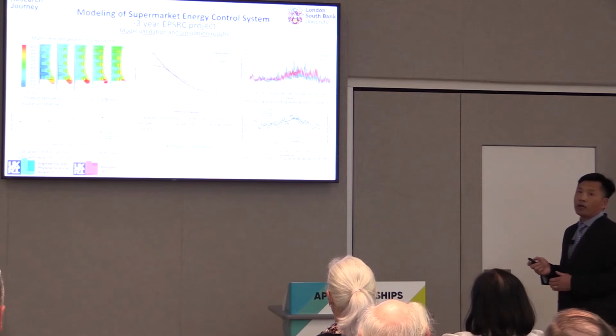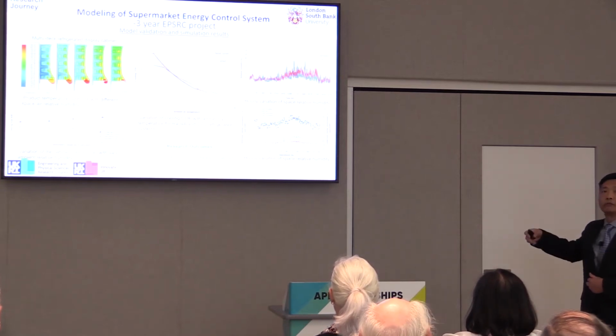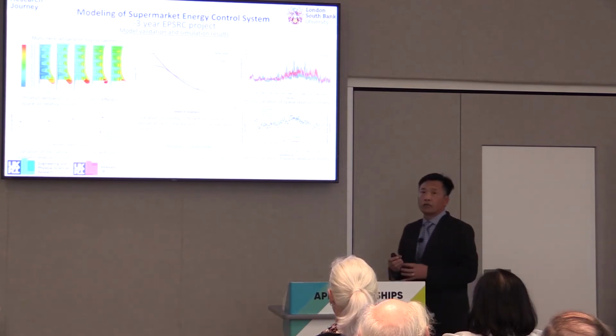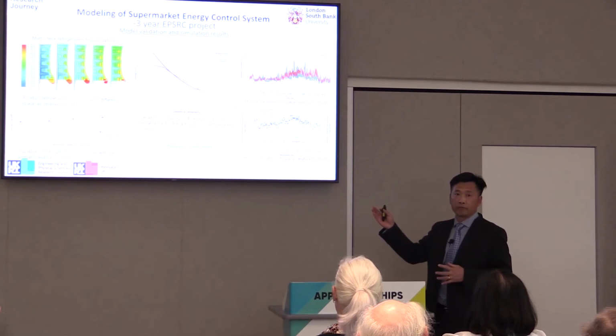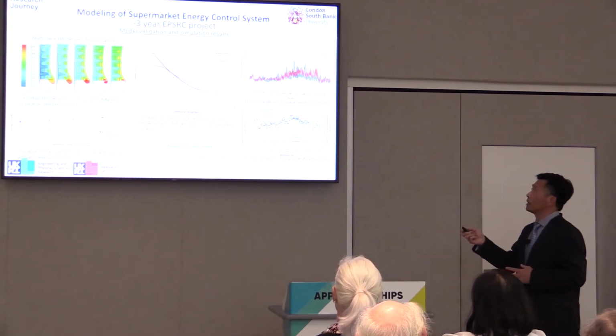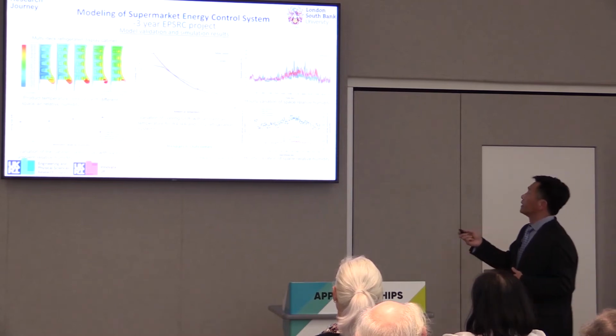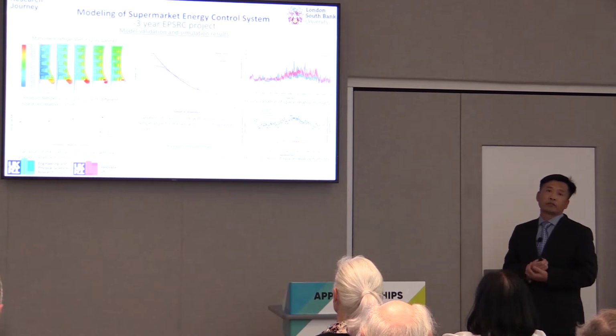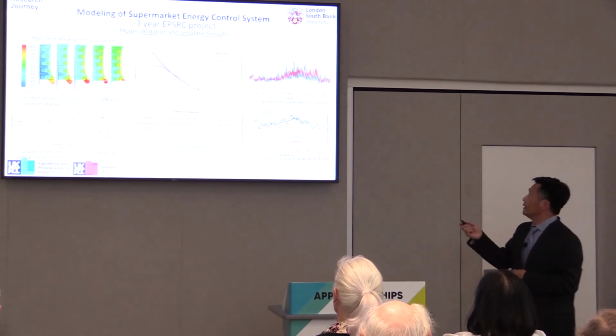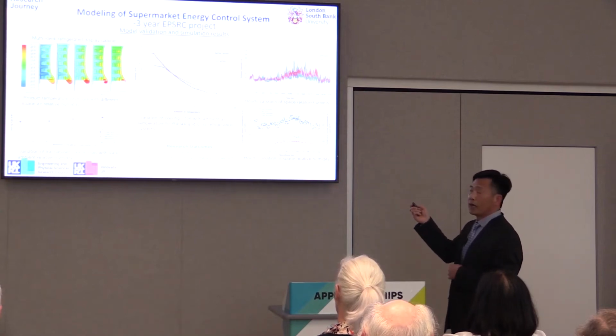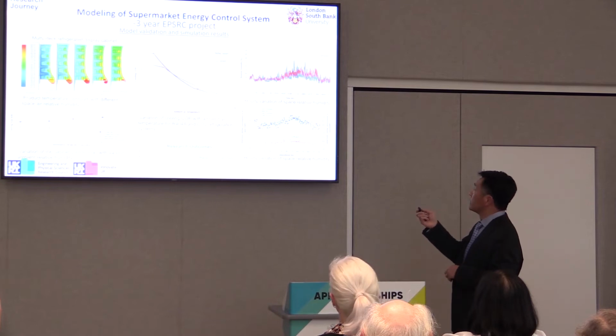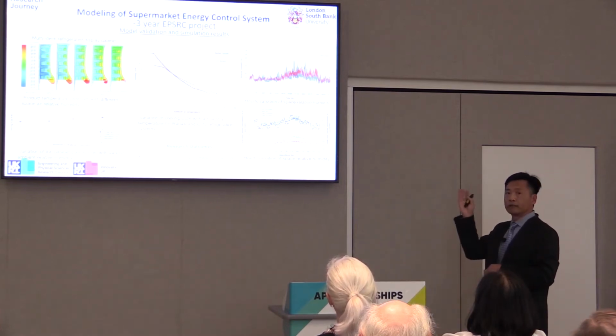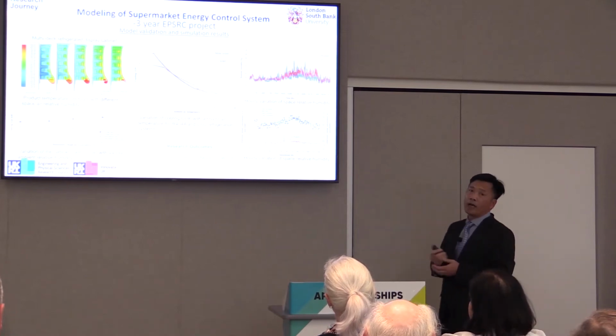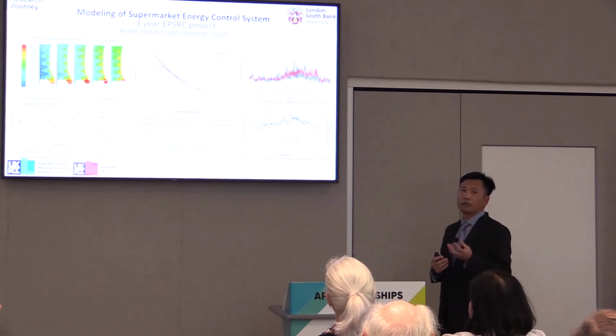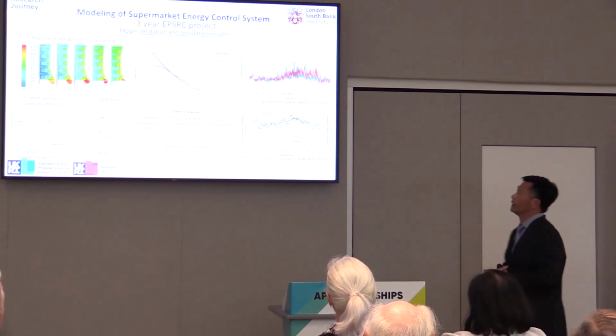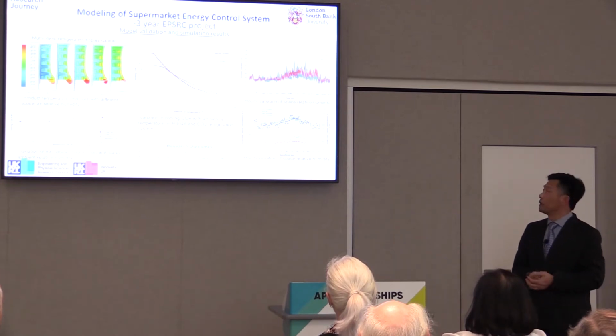Once we have developed the whole supermarket model, we can run it to predict the performance data and energy performance data for the whole year. We can obtain the hourly performance data and parameters for the whole year for the supermarket, and then compare with the measurements to validate our supermarket model. This is the simulation and measurement result for the indoor air relative humidity during the whole year, hourly. The bottom one is the hourly variation of the compressor power consumption during the whole year. You can see the modeling result matches quite well with the measurement.